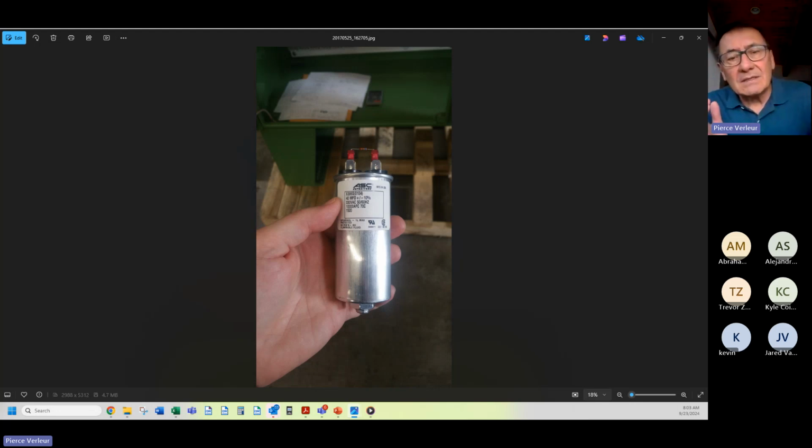My point in telling you this is when they paid us an ungodly amount of money to go down there. We didn't want to go down there. The point is that they failed to realize that the output characteristics associated with the tank circuit that we've talked about for this entire class, this is real. This isn't some salesperson trying to sell you VFD cable that you don't need. This tank circuit is a real law of physics situation. It has to be dealt with. If not, you've got consequences like I'm illustrating to you here.